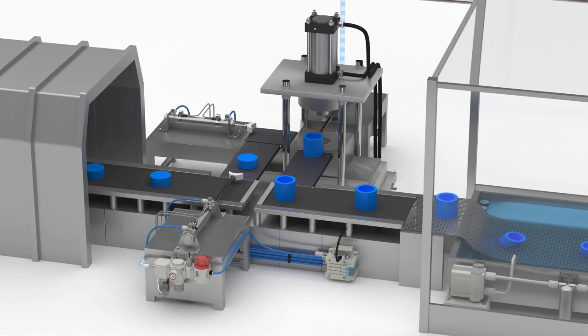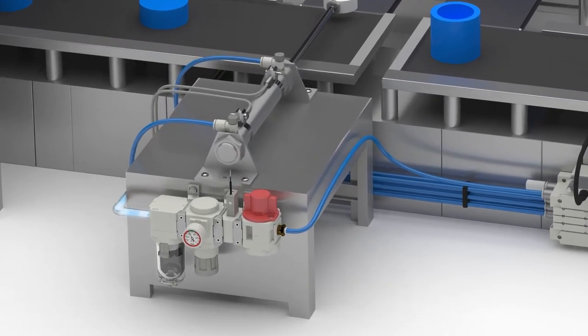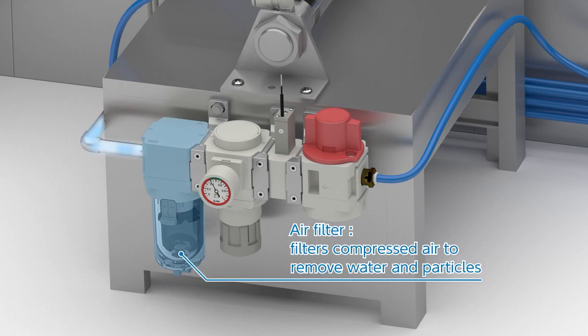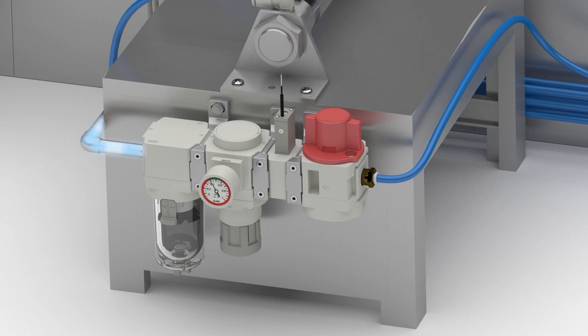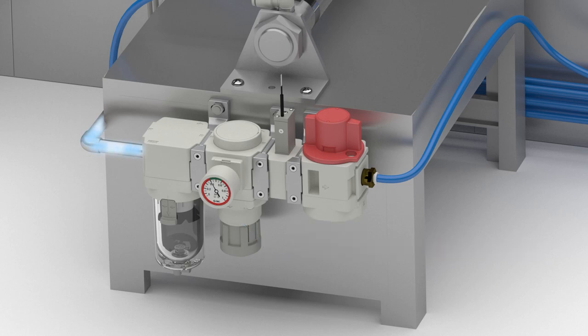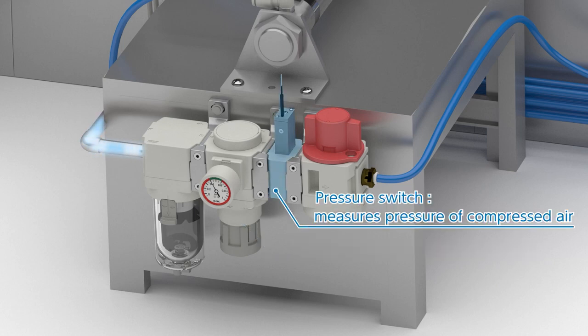The compressed air needs to be further processed for each application on a production line. It is first passed through a fine air filter to improve the purity of the air. The pressure of the air is then controlled by a regulator. And this pressure is then measured and monitored with the help of a pressure switch.